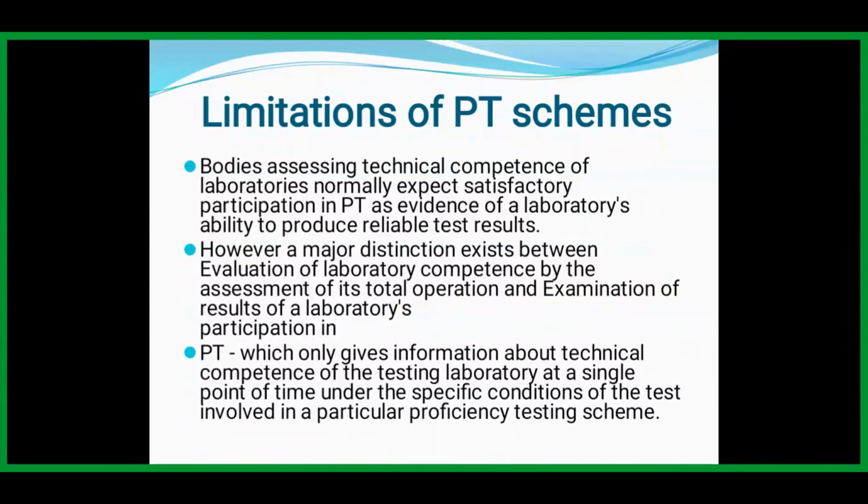Then what are the other limitations? All these schemes have been provided by the PT provider organizations. Bodies assessing the technical competence of laboratories normally expect satisfactory participation in PT as evidence of a laboratory's ability to produce reliable tests. However, a major distinction exists between evaluation of a laboratory's competence by assessment of its total operation and examination of the results of the laboratory participating in PT, because PT gives only information about the technical competence of the testing laboratory at a single point in time under specific conditions of the tests involved in a particular proficiency testing scheme, nothing else.